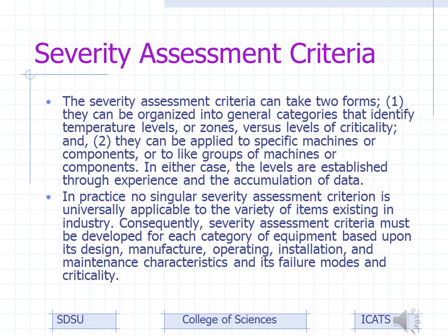I found a piece, let's say, of radar that was under light load at the time, and if it were under heavy load, it would mean we were under severe threat in the United States. The criteria was moved up quite a bit to make a problem something that needed immediate attention versus a low level because of that factor itself. This is a mission critical piece of equipment, and with heavier load, that hot spot that was identified would have become more critical and possible to fail, and that failure would have been catastrophic to the United States itself, and that's not overstating the issue.